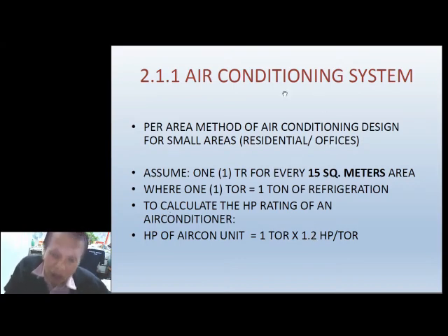By the way, this horsepower is different from mechanical horsepower - this is electrical horsepower. There's a conversion factor of around 4 point something, but that's not right to use here, because it would become too large. If you multiply 1 TR, 1 ton of refrigeration, by 4 point something, it becomes way too big. Imagine a small 15 square meter room with a 4 or 5 horsepower aircon - that would be too much.